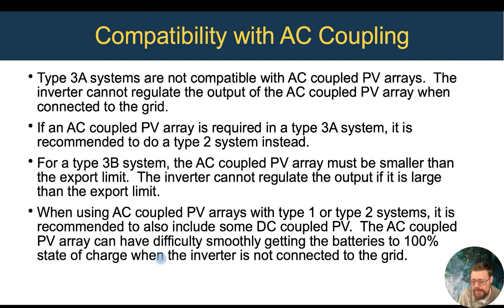And if that never turns on because the battery state of charge isn't going up, then the PV array can't turn on. If you have some DC coupled PV, even though the inverter has shut off the AC output because of low battery, it will still accept that DC coupled PV array, start recharging the battery, and once it gets up to the recovery state of charge, it'll turn back on, also turning your AC coupled PV array on at that point. So for that issue of not getting stuck in a low voltage disconnect situation, I always recommend having some DC coupled PV on an off-grid system, and a type 2 system essentially being an off-grid system.